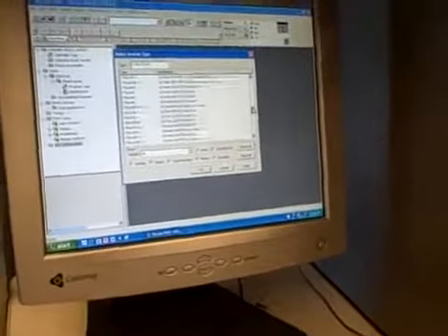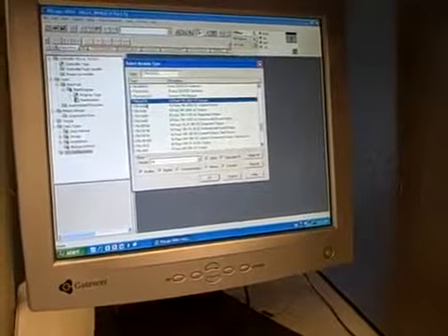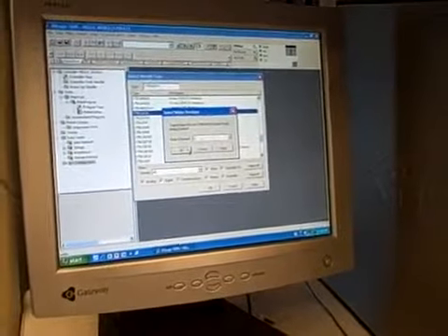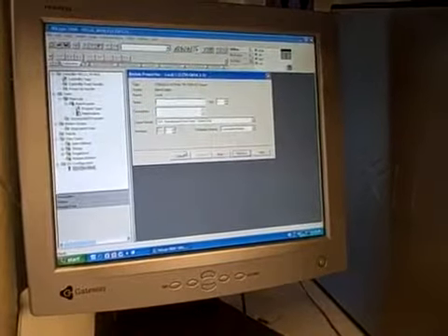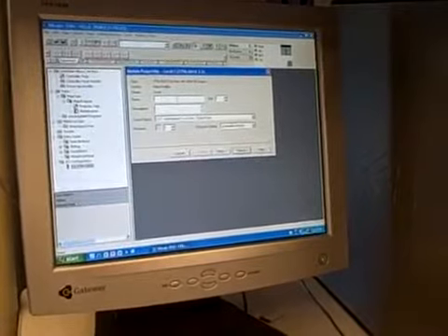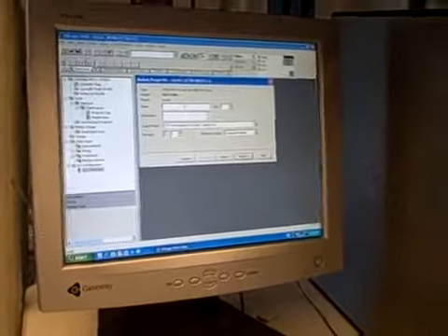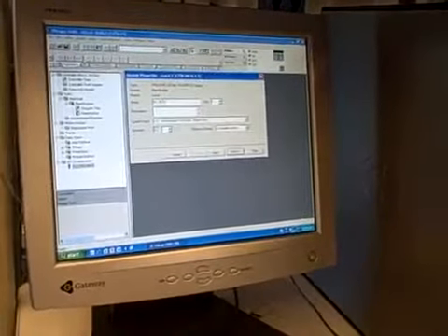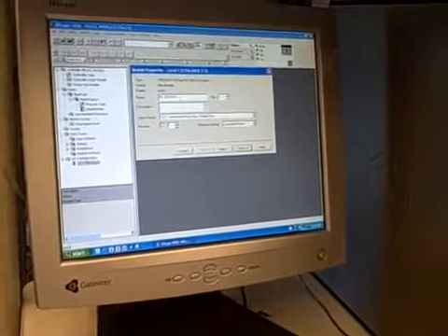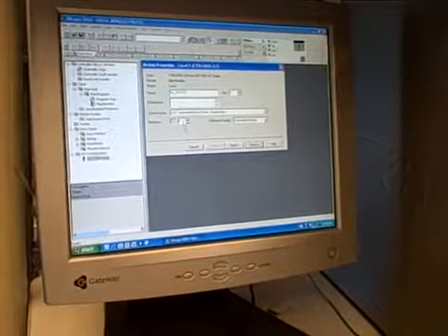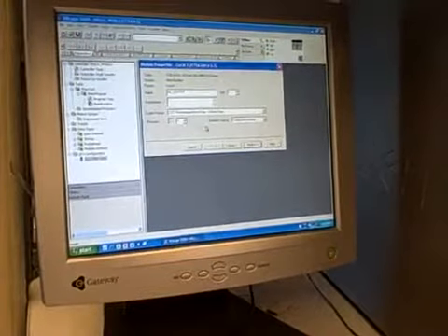So we come down here, and we select the 1756-OA16 out of this enormous list. Right there, click OK. Major revision 2, I know that happens to be correct for this I/O module. I have to give the module itself a name. This is going to be important for some applications. I'm going to call this AC output. I can even give the module a description if I wish. I'm not going to do that here. Revision level 2.1, that's okay.